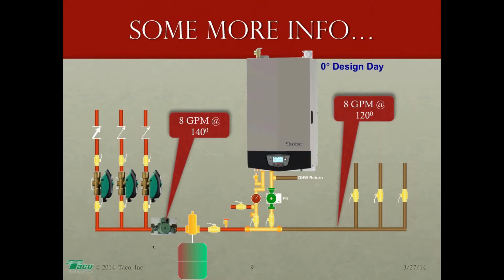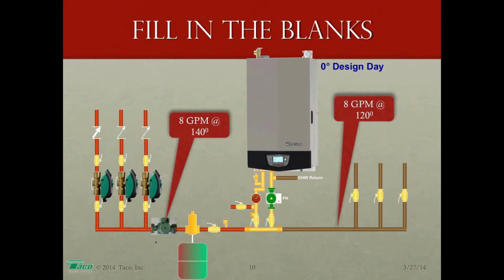0-degree day, 8 gallons per minute, 140 going out, 8 gallons per minute, 120 coming back. I check my specifications for the boiler, and I find that the required boiler flow rate is 5 gallons per minute. The required boiler flow rate that I need to pump through here is 5 gallons per minute. So what does that mean? We fill in some more blanks. Understand how closely spaced T's work. I have 8 gallons per minute zipping across this return leg right here. At this T, with the boiler circulator operating at a rate of 5 gallons per minute, I will now have 5 gallons of 120-degree water leaving my header going into the boiler to be reheated. So I have 8 coming back, 5 going to the boiler.